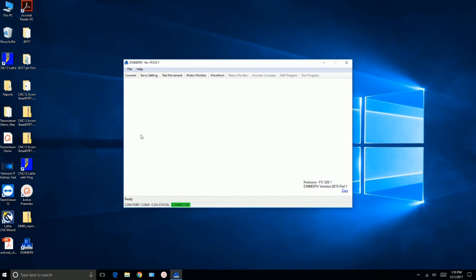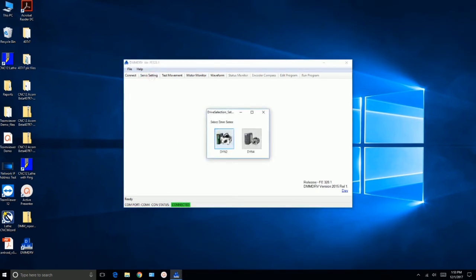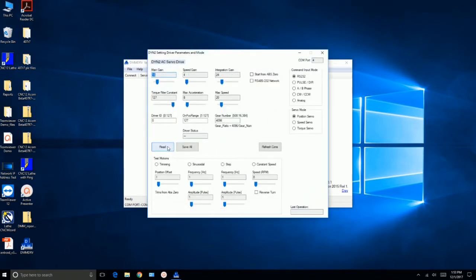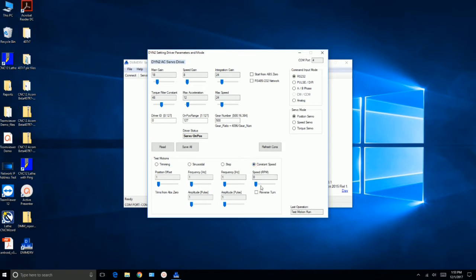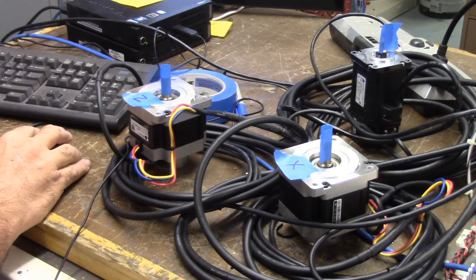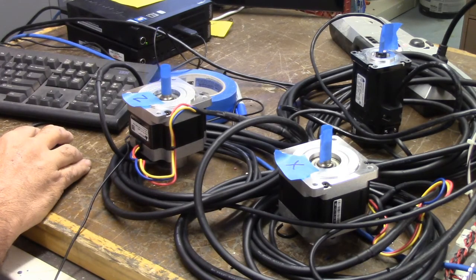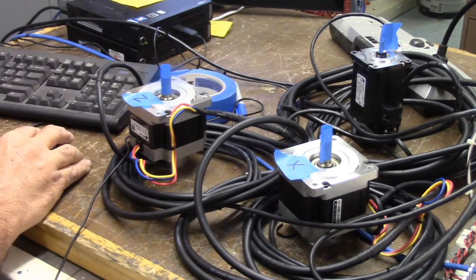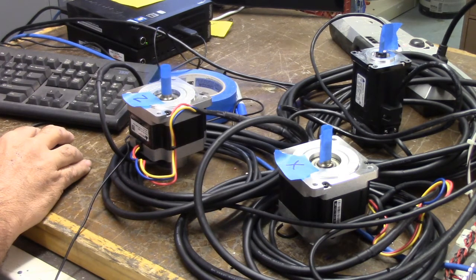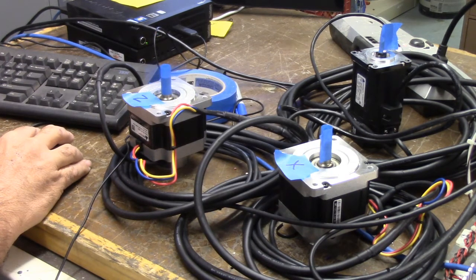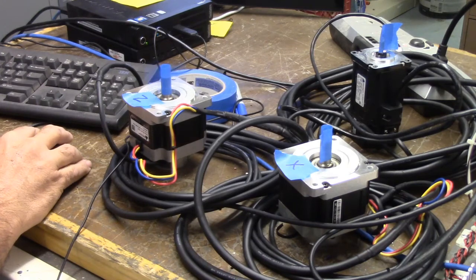Now that we're connected, we go to servo setting. DYN2. We want to read from the servo drive. And here's all the parameters. And let's do a quick test of the motor. We click on constant speed and then we can gradually run it up. You don't want to run it up too fast or above the motor's rated RPM. There you can see it's running.